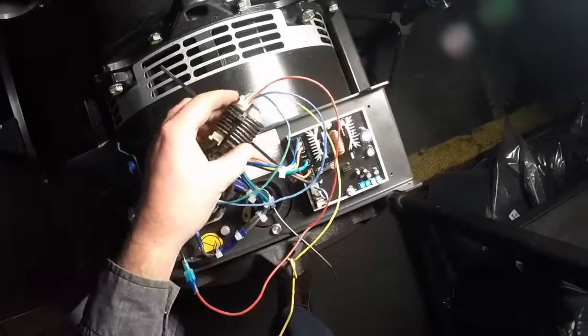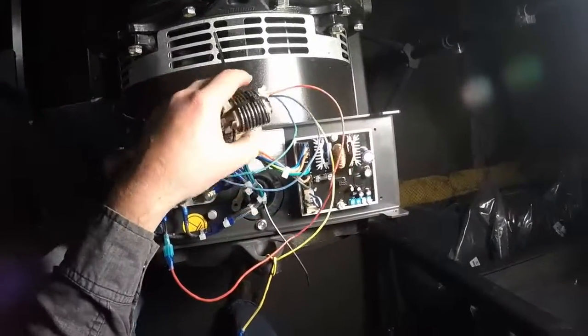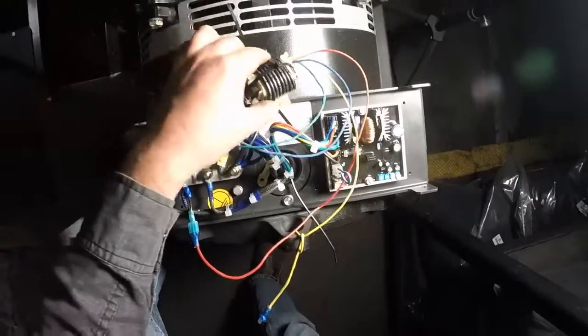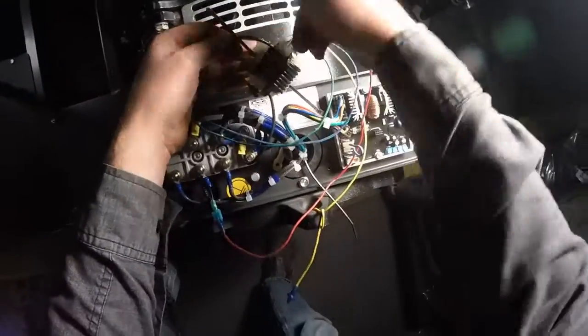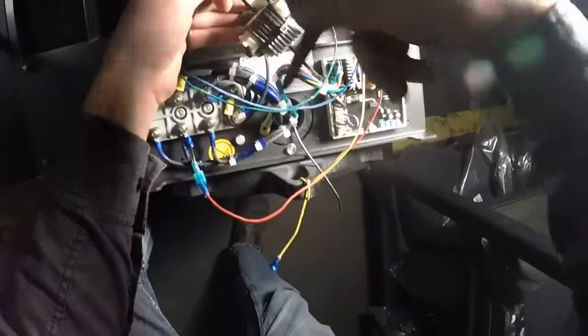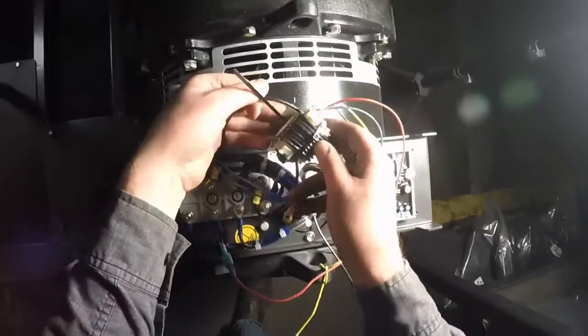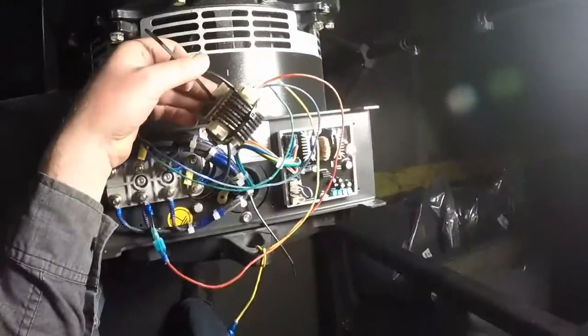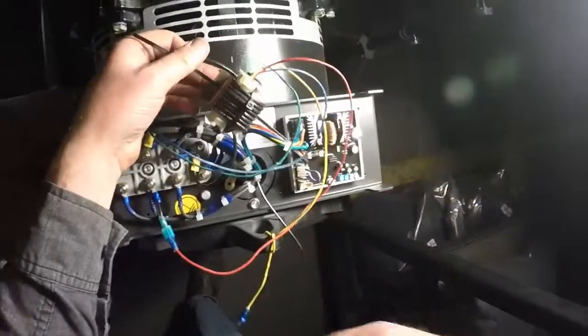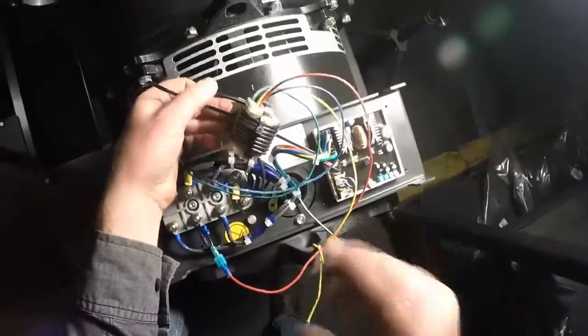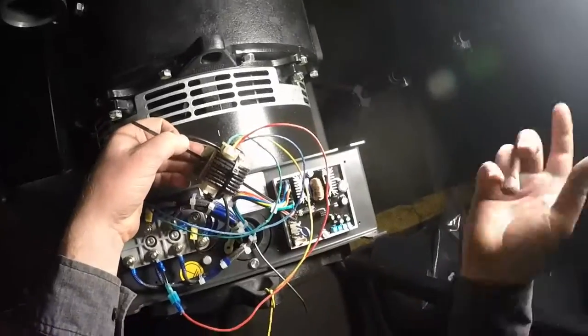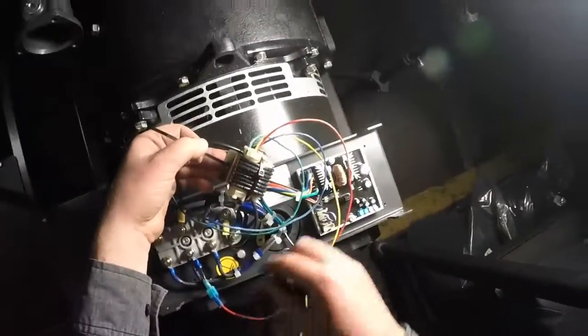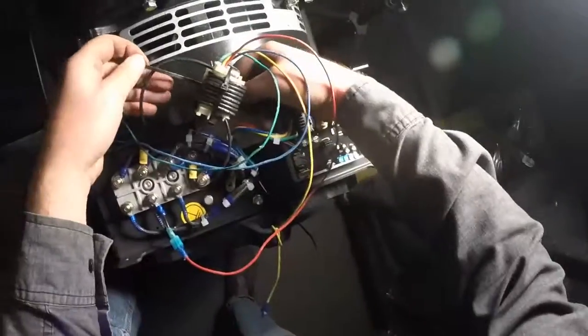So also to note, in this case, we can pretty well check for the way the current transformer is wired, because we can see how the coil is wrapped around. So you can also double check that the geometry of the current transformer is at least consistent. Make it consistent across everything. If you get an immediate high current behavior, then things are flipped around the wrong way. Reverse everything into the other orientation, and you should be good to go.